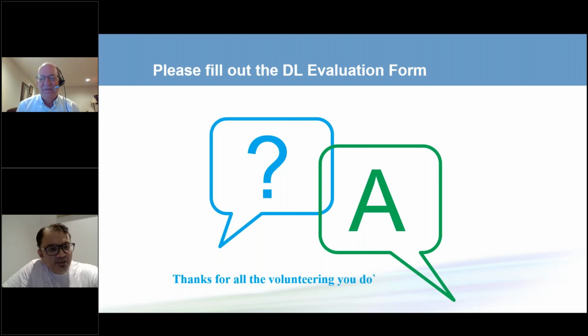Please provide the COP requirement at a high ambient temperature of 50 degrees Celsius, and the possible applicable correction factors required for AHRI, which considers 35 degrees as ambient. Sure. For screw and scroll chillers, the COP required is the same because they're the same pieces of equipment. They will use more power at those higher conditions. How much more depends on the specific compressor type. I hate to give rules of thumb because then people use them. It's best to work with the chiller provider to get the actual data, because then you'll make the best decision. But I will say between 1 to 1.5%, pardon me, let's do degree C, 2% per degree C increase in chiller power would be a decent rule of thumb.